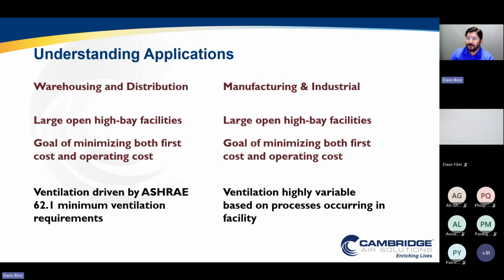But in manufacturing industrial, this ventilation can be extremely high. If I have a very dense, process-intense manufacturing environment, I may have very high requirements for ventilation and makeup air driven by process exhaust, ovens, other types of heat capture or indoor contaminant capture, which can be highly variable based on process. So I may have big open spaces on one side with little outside air requirement, and on the other side, a high amount of outside air requirements. That varies tremendously from unoccupied to occupied, or even from shift to shift.